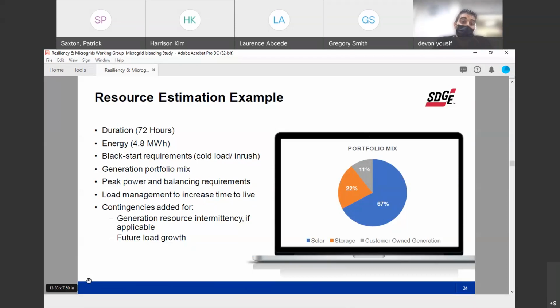Another thing to take into consideration is black start requirements. As I mentioned before with three-phase motor loads, when you turn on equipment from an offline state—going from a black start to turning on all these customers—it's not like a steady state where you have constant current running these equipment. These things will multiply 1.5, 2, sometimes 3 times their original current initially when turning on. So we need to take this into consideration and make sure our resources can withstand that kind of initial load pickup.